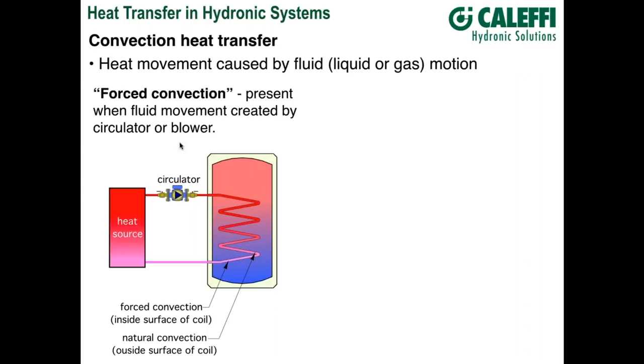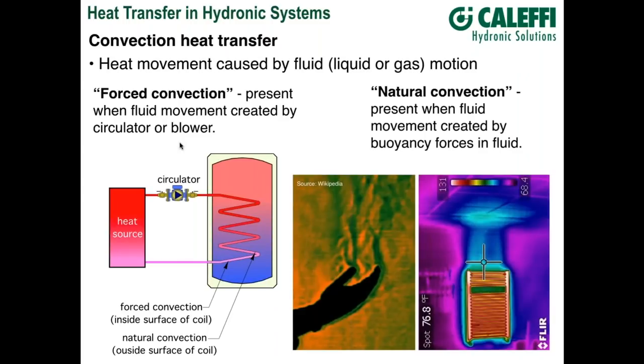For example, a circulator pumping hot water from a heat source through a coil in a tank produces forced convection on the inner surface of that coil. But on the outer surface of the coil, there's no circulator — any movement of the fluid is caused by buoyancy differences. As you heat a fluid, it expands, its density decreases, and it tends to rise. That movement is very gentle and slow compared to forced convection — forced convection on the inside, natural convection on the outside.